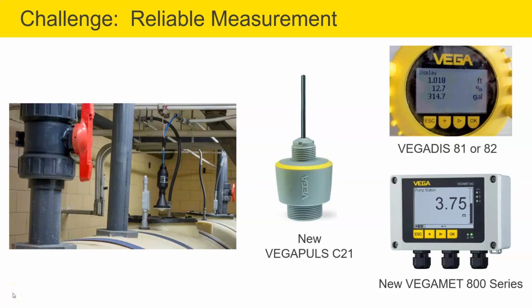Because the customer in this example wasn't sure of their exact level, they always had to send an operator down to the basement when the chemical supplier was refilling the tank in order to watch and make sure they didn't overflow. They could also only fill the tank about 75% full because of the blanking distance associated with the ultrasonic unit.